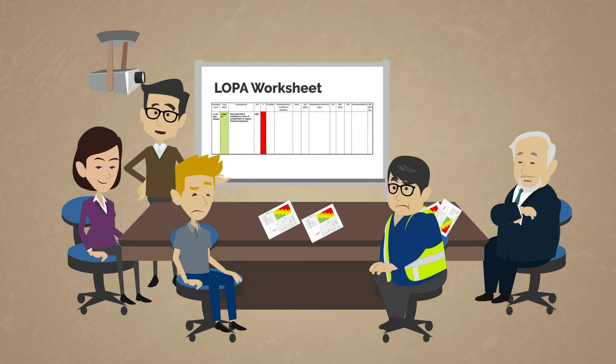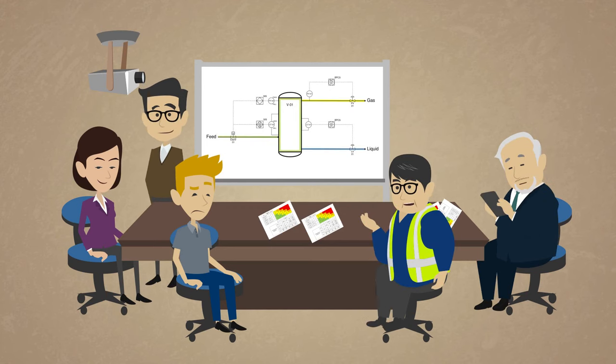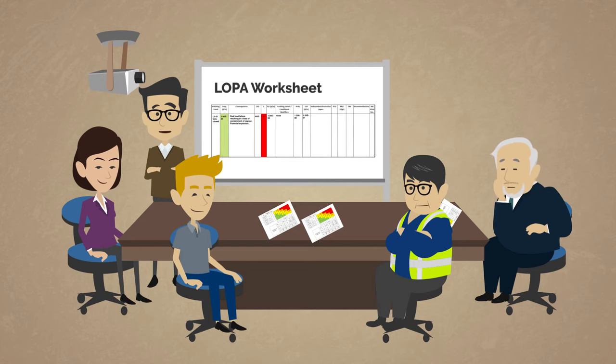How often do we expect personnel to be in the area? This will not be a highly trafficked area of the facility. However, I think that it's unlikely we could say that someone will be in the area less than 10% of the time just based on operator presence. Alright, then we can't take credit for a conditional modifier.